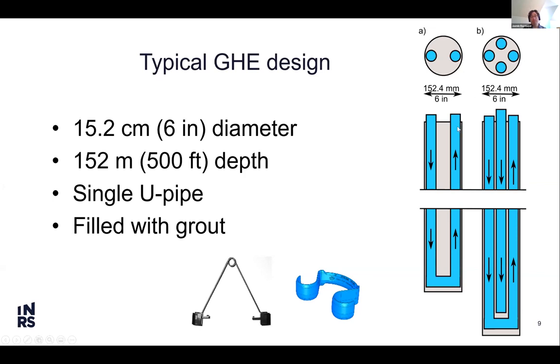But there are alternative designs, such as a coaxial pipe, where you install a small pipe inside a large pipe and flow inside, but this is more complicated to install in the field and drillers don't like it. Another option is the double U-pipe. Instead of a single U-pipe, you have a double U-pipe, with more pipe area that allows greater heat exchange. Also there is more fluid inside the borehole, so a thermal mass of water that can impact the performance of the system with more heat storage capacity in the borehole.